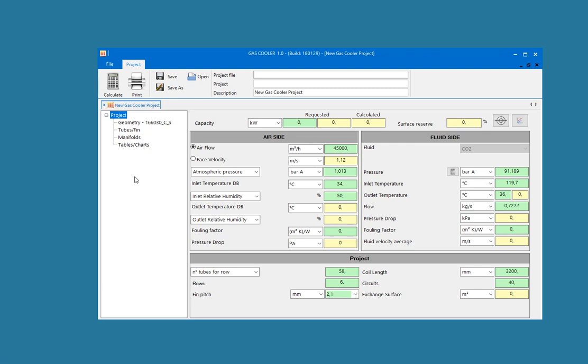Unilab Transcritical Gas Cooler is designed precisely to operate in transcritical areas of transformation. In fact, the software divides the heat exchanger into 100 pieces and for each piece makes a thermal balance. This means the thermodynamic properties are not an average between the beginning and the end of cooling, but vary for each piece, for each step.